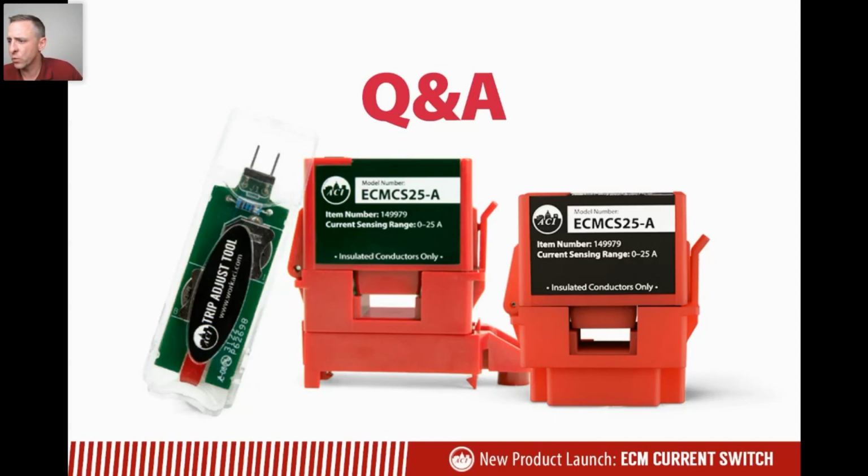We can certainly help you with that as well. Another question is, how does the trip adjust tool work? I've mentioned that briefly before, but I'll go through that again because it is unique. The trip adjust tool is a feature of this product. It's not a bug. This was designed in order to get the trip point of this device as low as possible. We removed the LED light, so it minimizes the power consumption of this device. This device just connects to the terminal strips on the ECM current switch, and it provides an LED that tells you when the relay on the current switch itself is energized or not.